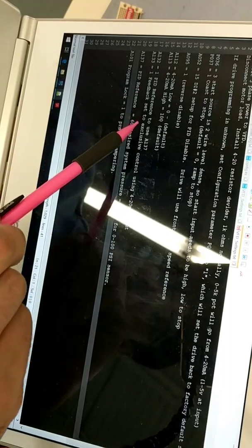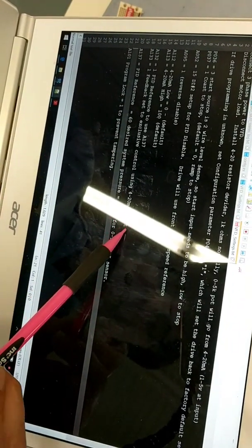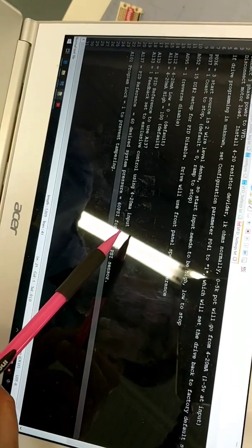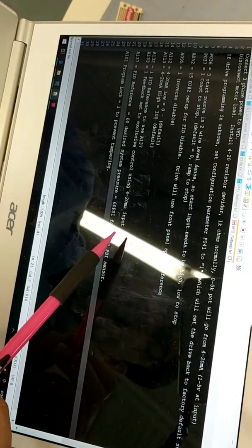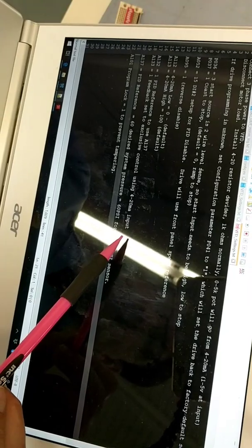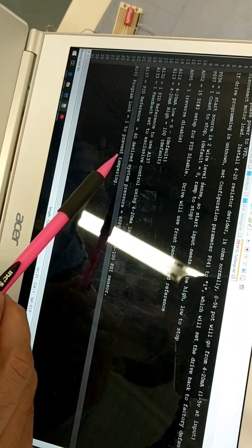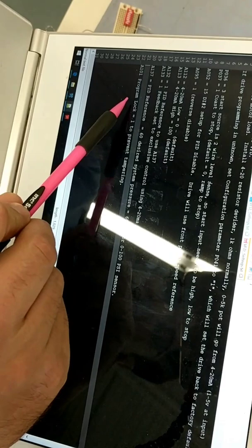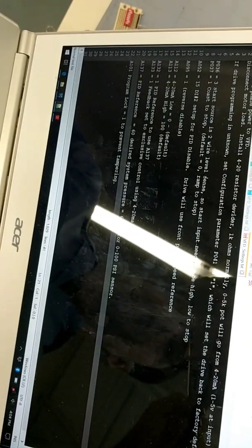Going back up here, A133 is setting the feedback to the 4 to 20 milliamp input exclusively. You could also set that as a trim setting where it may use another control source like the drive potentiometer on the front panel, and then use that to just trim the output for the feedback. And lastly, to prevent tampering, you can set A101 to a 1. That's program lock. So we'll go ahead with the programming here.